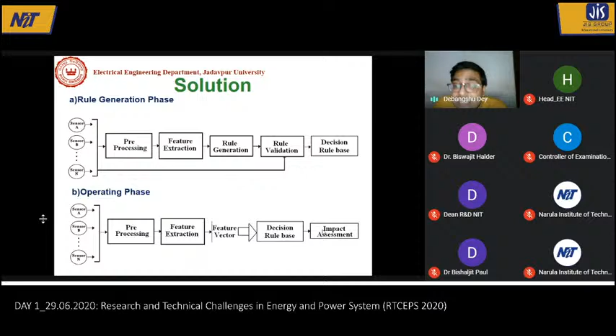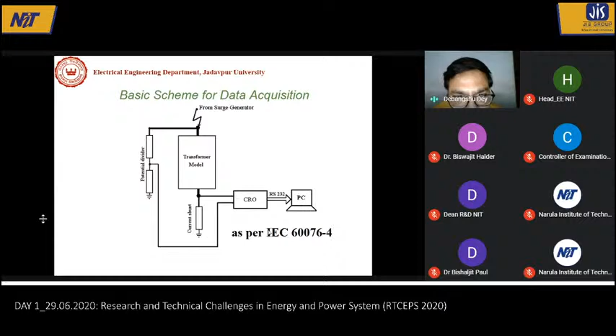So the first example I'm showing, I have shown you three examples: one for the impulse waveform analysis of a transformer, then partial discharge, and then online, cellular network based remote monitoring. So here the same diagram, the data was actually recorded as per IEC. This is the IEC number. In this particular IEC standard, the testing procedure is described. According to that standard, we have to apply some voltage, and we have to record some data, and we have to know what the condition is.